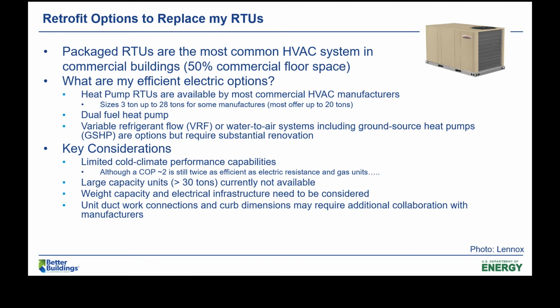Now, there was some interesting feedback, I was writing down notes as the poll was going on, and I might not have done a perfect job, but there was no discussion or concerns about the performance of heat pumps, which kind of shocked us initially. Heat pumps, for these rooftop and package units, are extracting heat from the outside air to put it into your building. That's fundamentally what they're doing. So there is the reality that the efficiency of these units does go down as they're exposed to colder air.